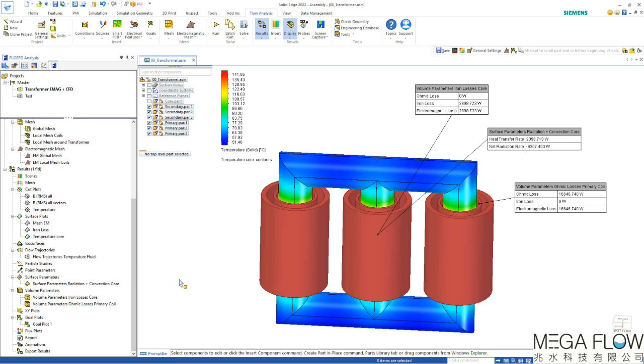With this type of simulation you can couple electromagnetic simulation with fluid flow simulation all within one tool, within one solver run, running on an iterative basis. You don't have to do iteration by iteration because the electromagnetic changes are considered much faster than even transient CFD simulations. Therefore these type of iterative approaches only work on several iteration bases like 25 as we have said in this model.